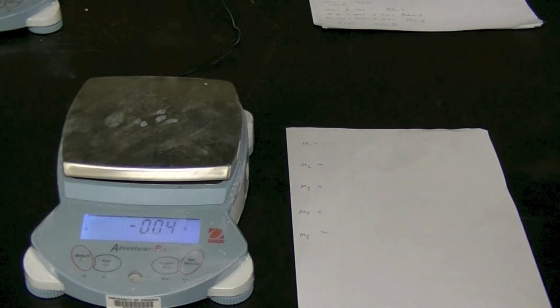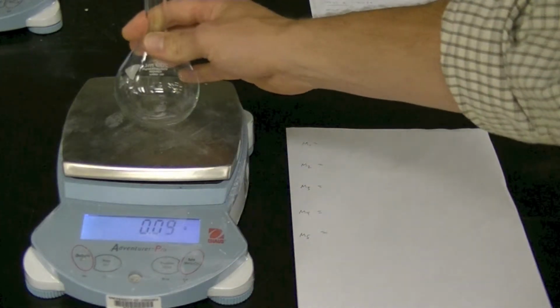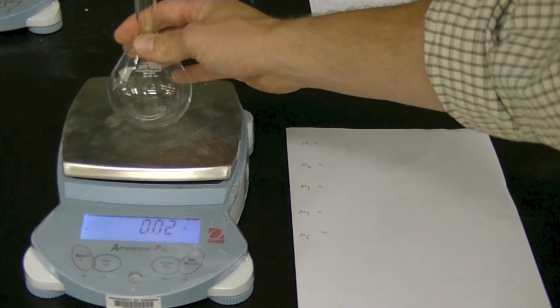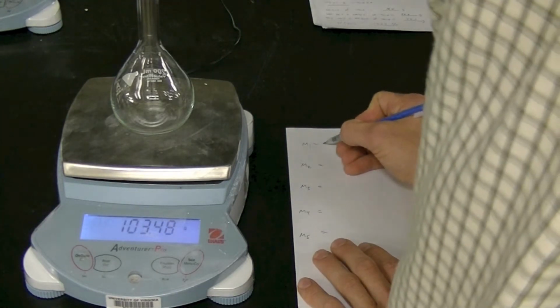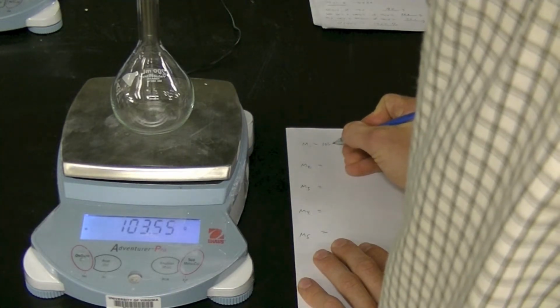Calibration of the pycnometer is a two-step process. The first step is to calibrate the mass of the empty, dry pycnometer. To do this, we must make sure the pycnometer is clean, empty, and dry. Determine the mass of the pycnometer and record. The scale must be accurate to 1/100th of a gram. Repeat the weighing process, totaling 5 separate times. Record all 5 measurements.